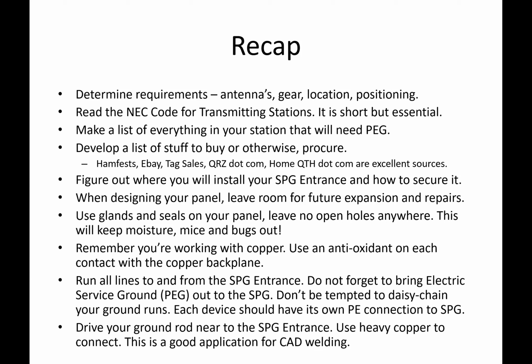Remember you're working with copper. Use an antioxidant on each contact with the copper backplane - copper will tarnish very fast in the elements. So if you do a good job sealing up, also use a little bit of copper antioxidant grease that will help preserve the connection going forward.